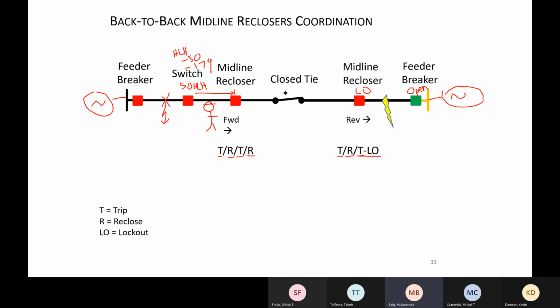Okay, so let's suppose they're shifting their normally open breaker from right towards the left, making the left one the normally open. Do you think they will have to shift the relay lockout condition from right to left also, or will the forward and reverse be opposite also? Well, it's just naturally what direction the fault current flows. So there's nothing changing other than, to do forward and reverse, the relay has to have a PT. At that point, it's comparing the angle between my voltage and my current, knowing that with a fault, voltage is typically going to lead current by about 90 degrees. So it's looking at that phase angle between the two to say, is the fault in front of me or behind me? That's all logic in the relay.